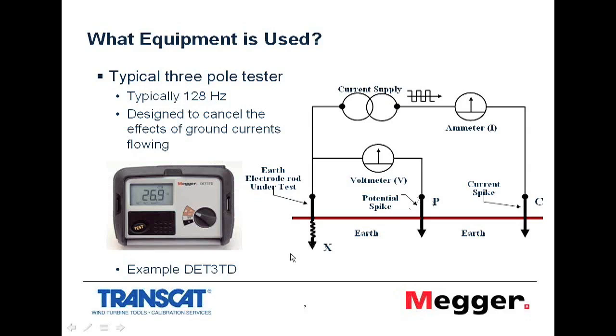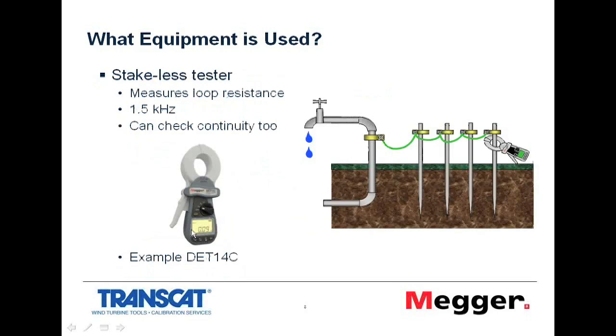So the key thing here is that the instruments are designed to cancel the effects of ground currents flowing in the ground. Okay, that particular instrument there, as you can see, is a 3-pole tester. We also have a different kind of tester altogether, a stakeless tester. As it sounds, in this case we're not going to place a P or a C spike into the ground. In this case, this current clamp here will inject a current into a circuit and then measure actually how much current is induced. Now there's 2 cores in the head.